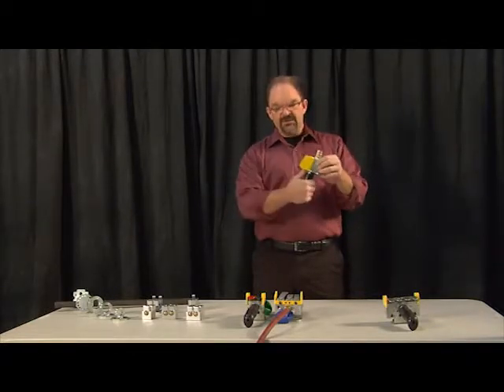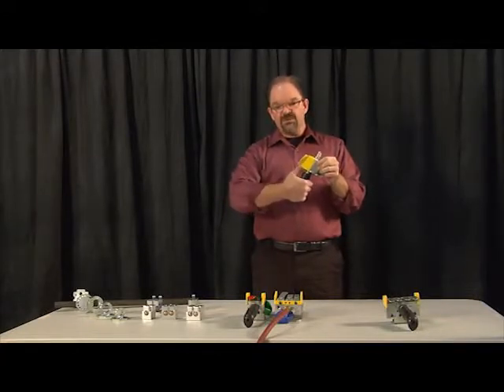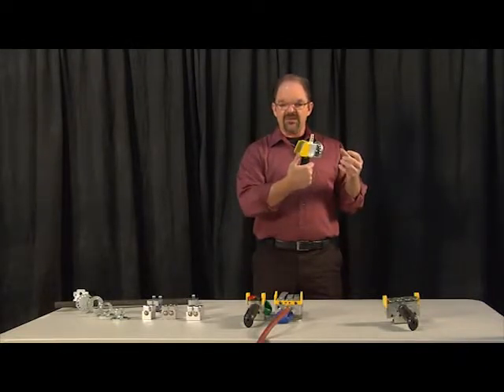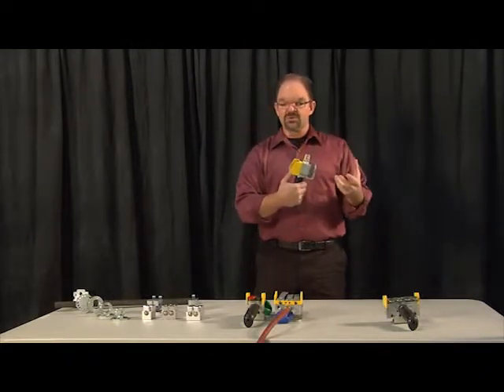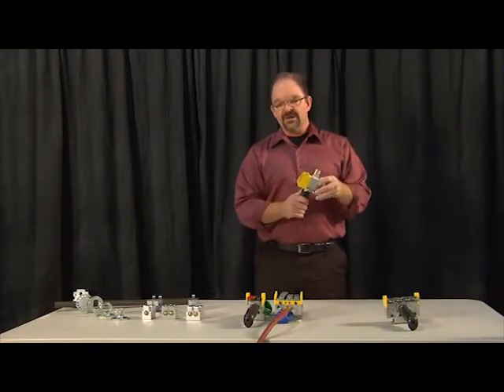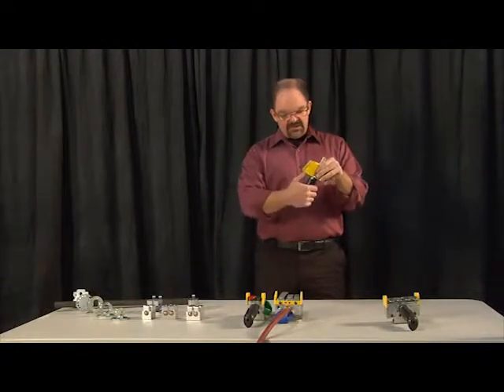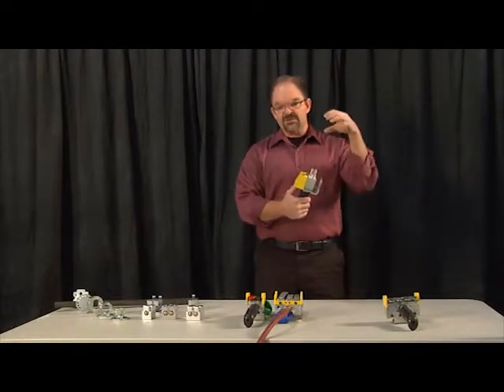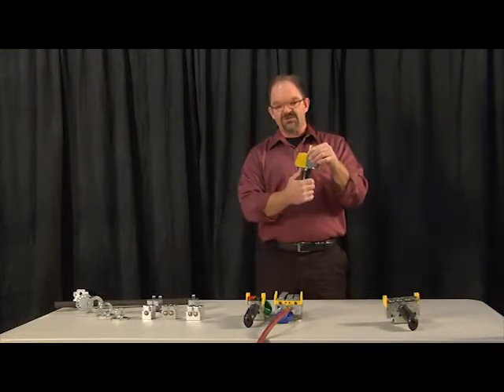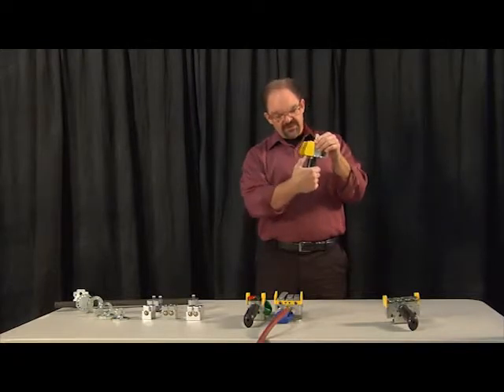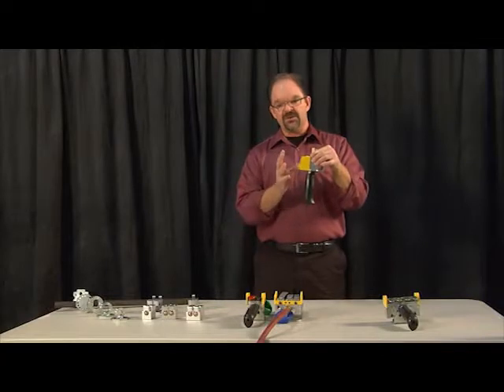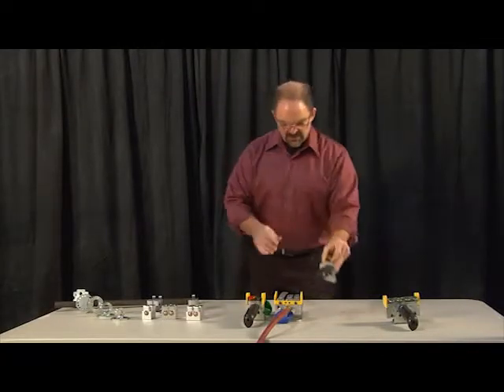Once it opened, I would have a lot of force on there and I would naturally want to go right down. That's why you're going to see operators in the field using a feathering technique to try to keep good control with that poppet valve. On the other hand, the spool valve, the incoming air comes in adjacent to the valve, so the valve is always the same. You get a good smooth depression force regardless of incoming air. You're going to be able to use that good control without any significant change in the startup and the movement throughout the entire stroke.